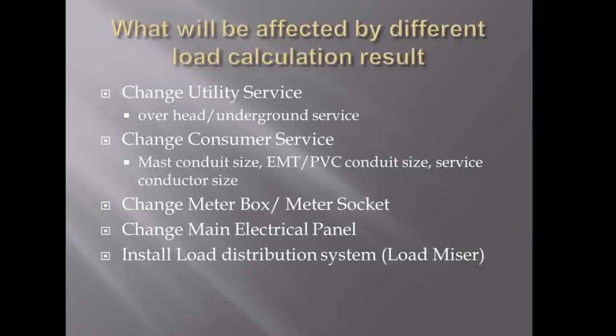If you cannot do a service upgrade, you may need to install a load distribution system — basically called a load miser. If you don't have enough power for your system, a load miser can balance your load. For example, if you have an electrical vehicle charger, you can use a load miser together with a range or a dryer so that you cannot use the two loads at the same time. That may be another option for you.